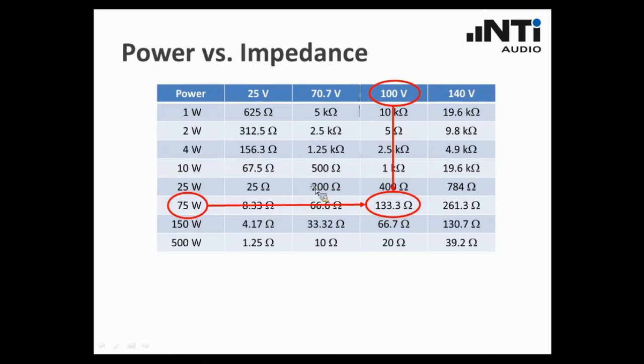Another information that we can get out of this table is what I have highlighted here with green bars. If we are in the range of very low systems impedances, you may imagine that the impedance or the resistance of the wires plays a more and more important role, because the overall system impedance is the combination of the loudspeakers and the cables. So if we are in this range here with the green highlighted part, then you must be very careful to use a wire with a wide cross-section in order to minimize the resistance of the connecting wires. Or if we express it in another way, it is better to have a system with a higher system voltage, because here you rarely encounter this problem of low system impedances.